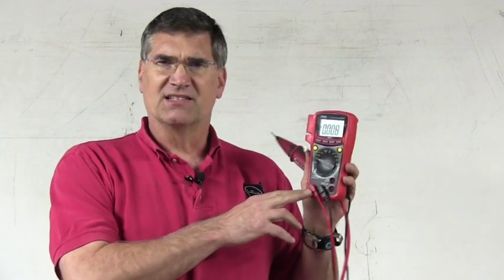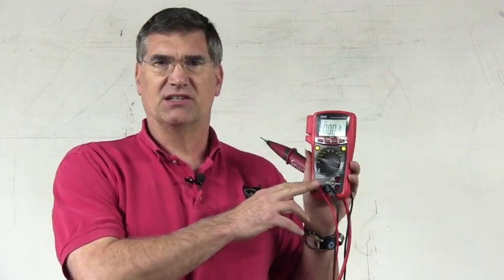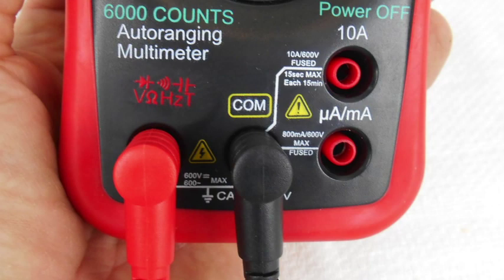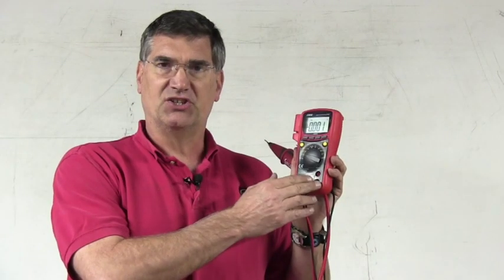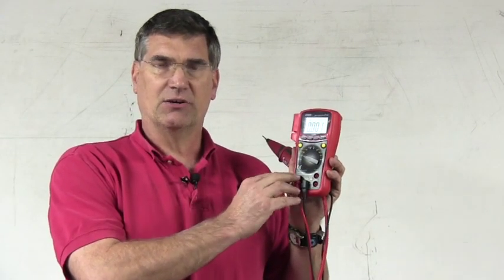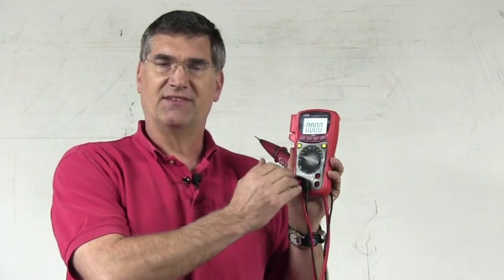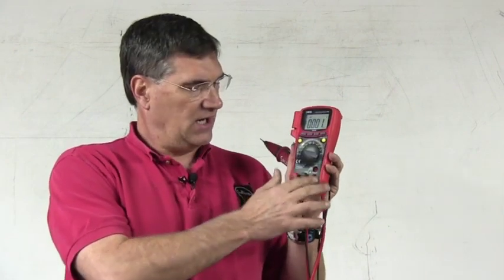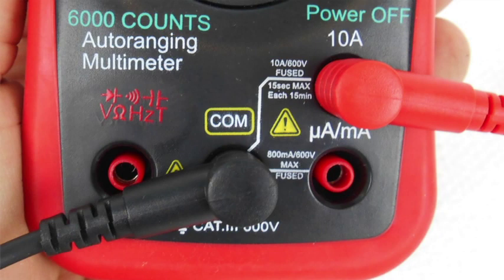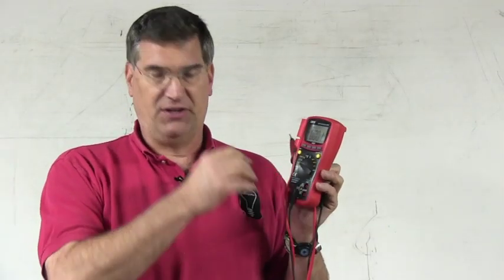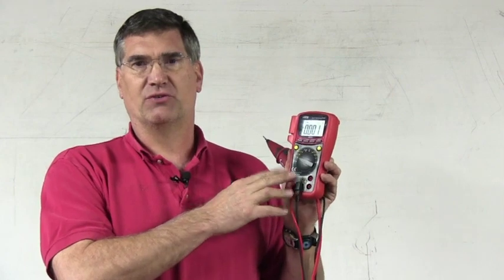First of all, it's a little different than most meters because under normal circumstances, what I'm used to is the voltage port being on the right, and on this meter, it's on the left. So you just need to be cautious that you remember that when you're setting up the meter, the voltage port is on the left and not the right. The amp ports for the amp meter connections are on the right, which is actually backwards from what I'm used to, but it really doesn't matter. It's just a different design feature. So make sure you're in the proper port for volts when you're trying to measure voltage.